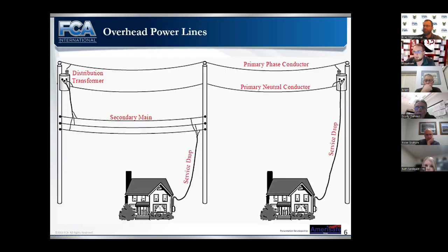But the point I always notice on this is that they did not come in contact with the power lines, and that's a common misconception. You do not need to touch an uninsulated line in order for it to arc if you just get close to it. The second misconception is that they were using wooden or possibly fiberglass rolling poles. So those don't really conduct electricity, do they? Yes, they do. Pretty much everything conducts electricity unless you have an extremely clean, non-conductive material. So a brand new wooden rolling pole is not likely to conduct a lot of electricity. Would it conduct enough to cause a spark that could ignite a flammable environment? Definitely.